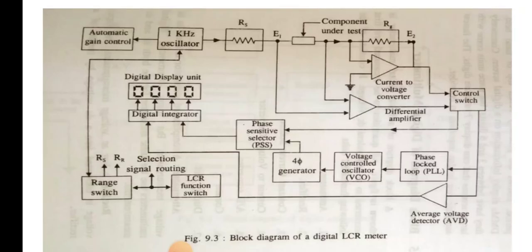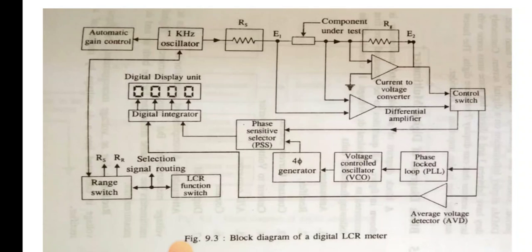The source resistor RS is connected to virtual ground. Because RS is connected to virtual ground, the presence of RG (the range resistor) does not change the value of the current flowing through the component under test. So the range resistor does not affect the current through the component under test.